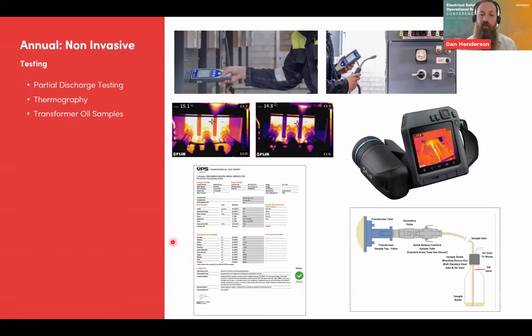I had a client recently where they were doing samples based on their own internal standards. So when I benchmarked them, there were some issues. They weren't doing DGA, so we're starting to indicate some dissolved gases in there. And additionally, they were doing acidity and water content, and actually they had a massive drop in dielectric strength. So what that meant was the actual insulating properties of the oil was starting to reduce quite a lot, which needed to be monitored and obviously acted upon at a certain point, because once it stops being an insulating medium, it'll just conduct, and that's where you're going to get a flash over the transformer. So these are things that they weren't testing for. So you've got to make sure you're testing for the right assets that you've got, for the right voltage and to the right standards.